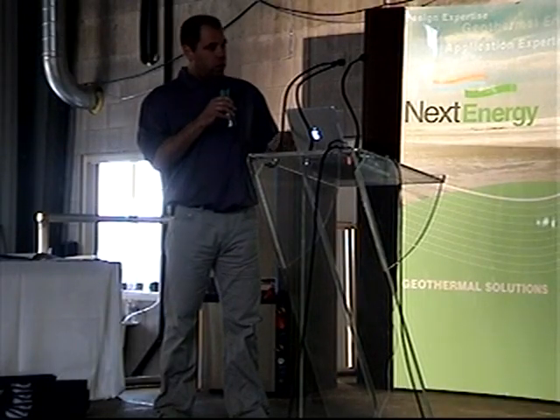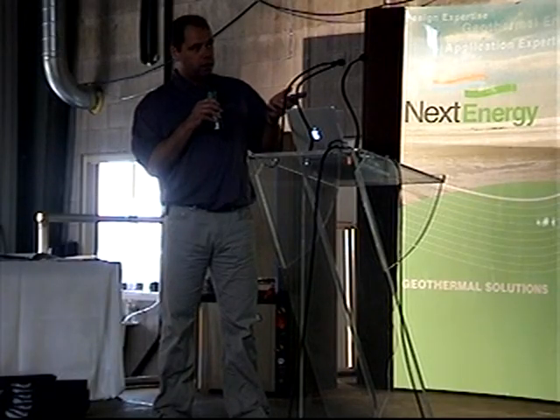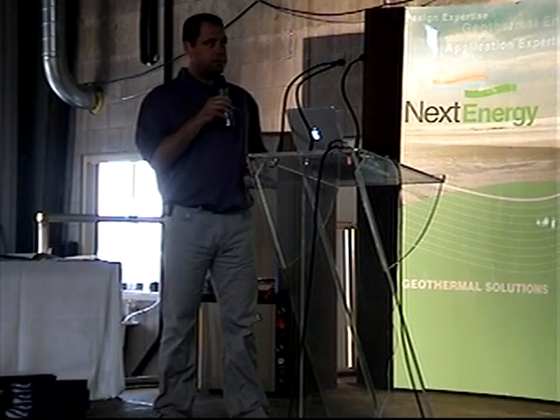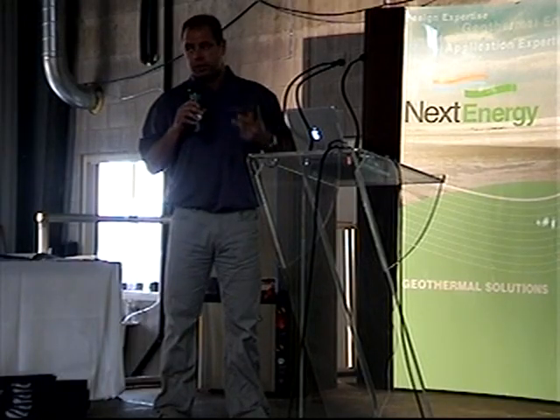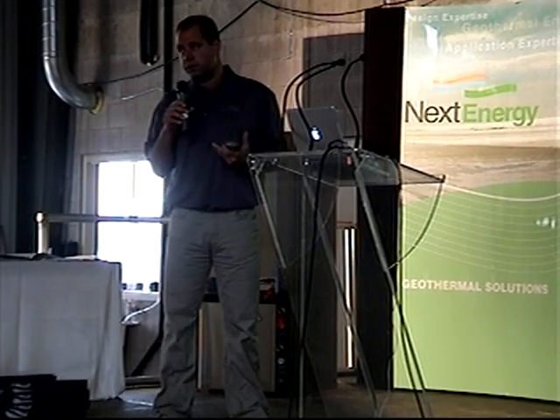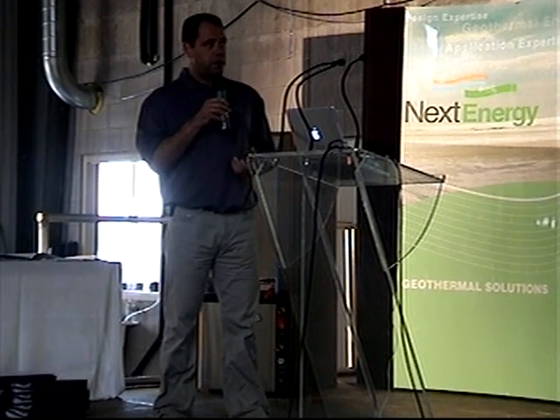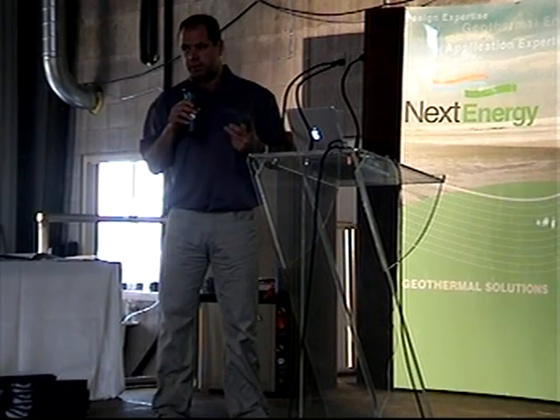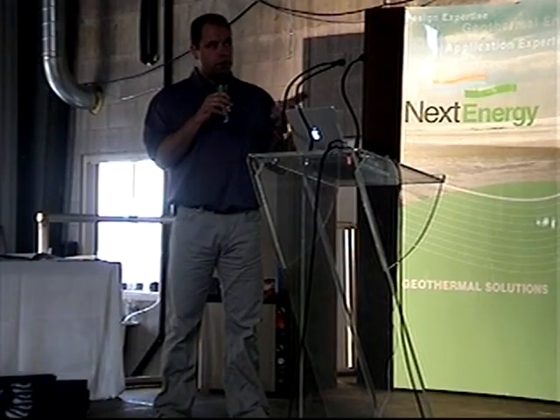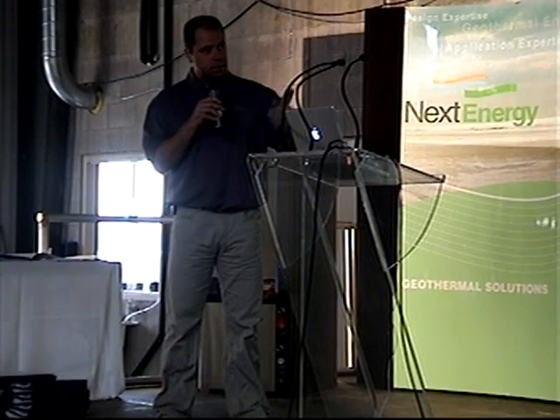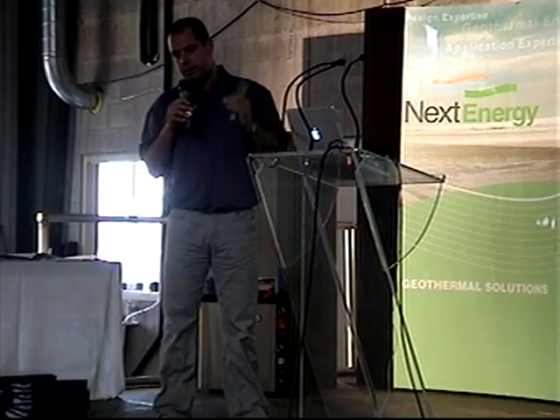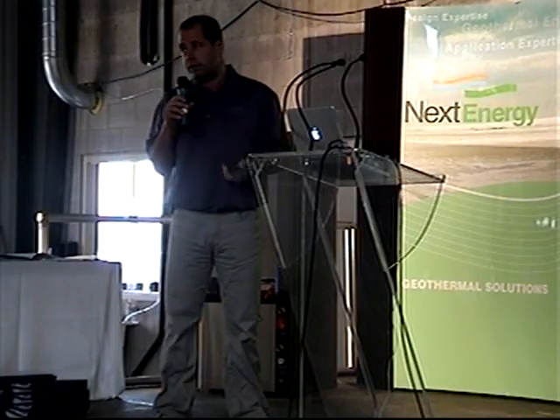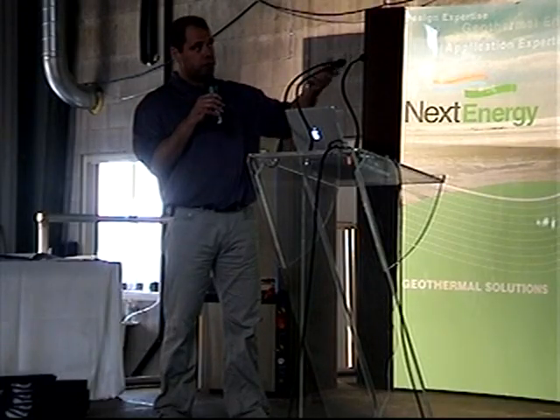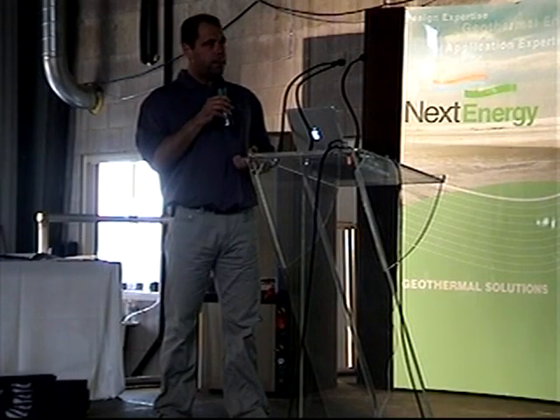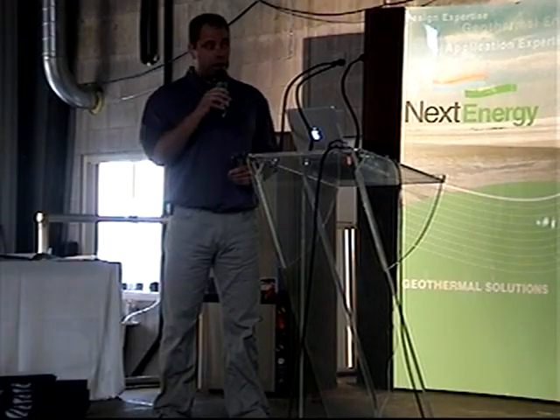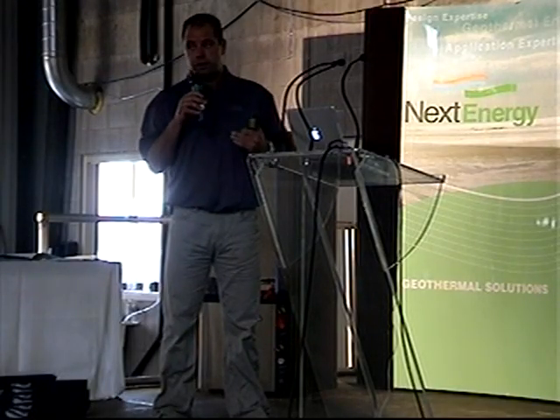So where you want to measure your superheat is on the line coming into the compressor, your suction line. And all you do is you put your gauges on the unit. You know what your low pressure is, your suction pressure. You'll need some type of a chart. Some gauges have it right on the gauges. You cross-reference that number. So say it's 80 pounds, R410. You look over what that number might be. It might be 35 degrees. You measure your actual temperature with a thermometer, and it will be hopefully higher than that. And the difference between the two is your superheat.